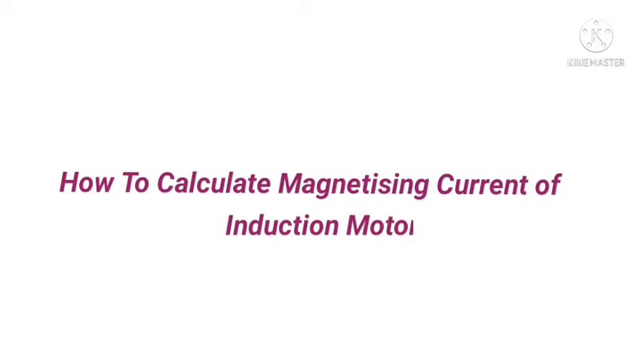Hello viewers, today in this video I will explain how we can calculate the magnetizing current of an induction motor. Whenever an induction motor is in operation, the total current drawn by the motor is always composed of two components. First one is the active component, second is the reactive, also called magnetizing component. Active current is always directly proportional to the useful output power delivered by the motor, while the magnetizing current is necessary to establish the magnetic flux or magnetic field inside the motor.